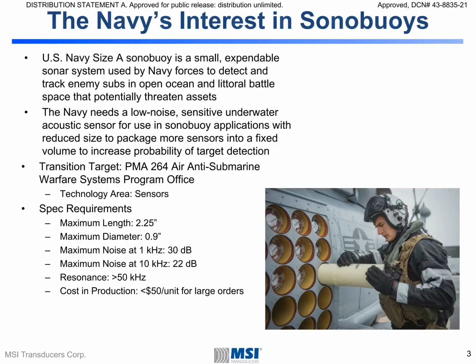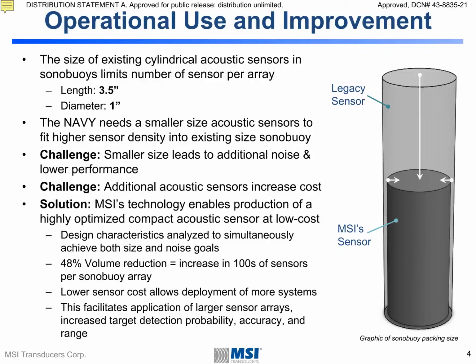The specification requirements for the new acoustic sensor are listed here, as you can see. The legacy acoustic sensor could not simply be scaled down, as reducing the dimensions of the sensor makes it physically challenging to meet the noise and resonant frequency requirements of the system. The size of the legacy acoustic sensor in light gray relative to MSI's new acoustic sensor in dark gray can be seen on the right. The dimensional difference is obvious.